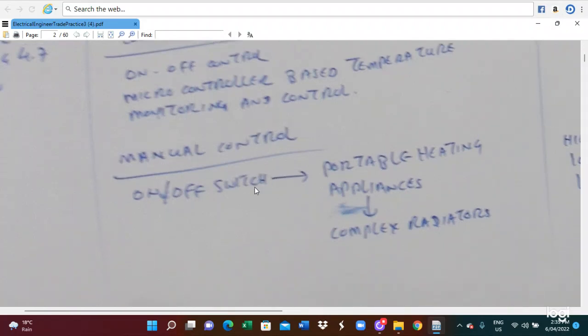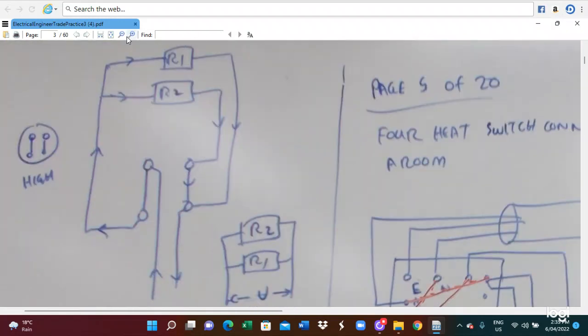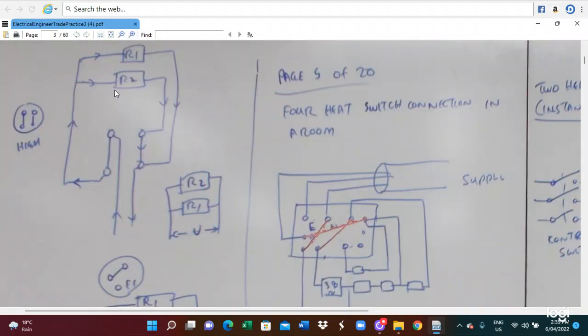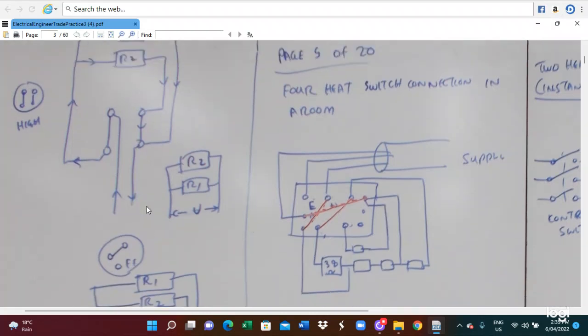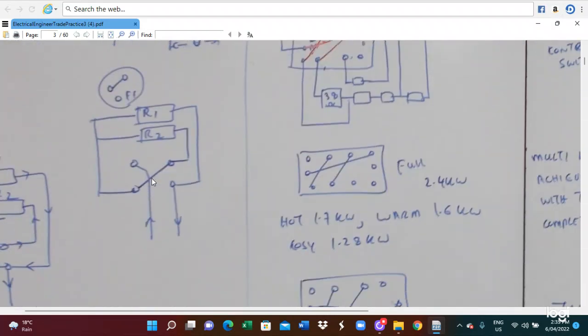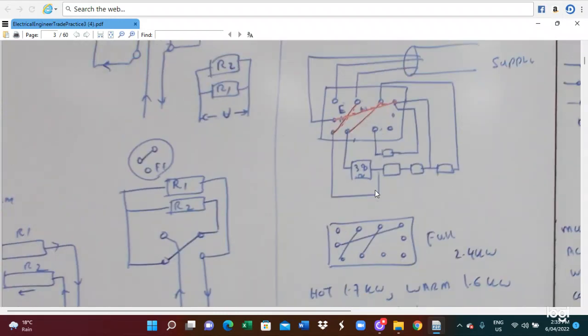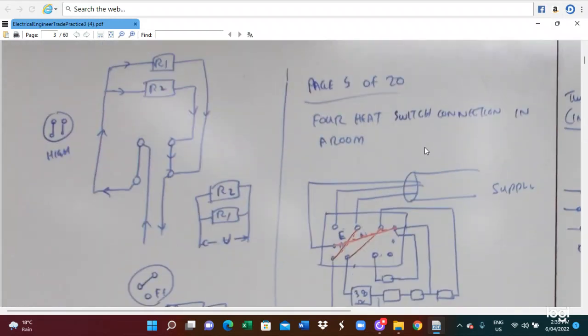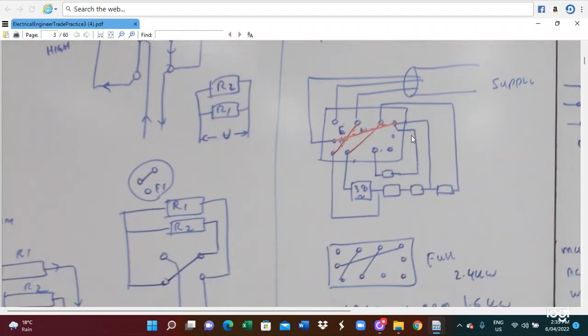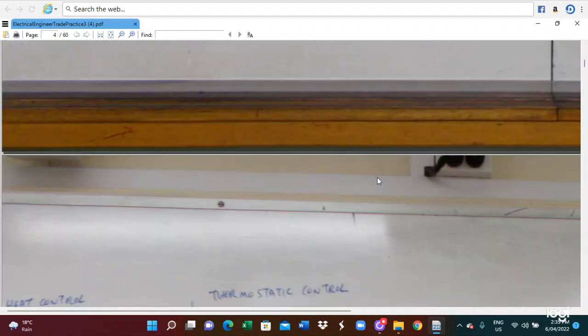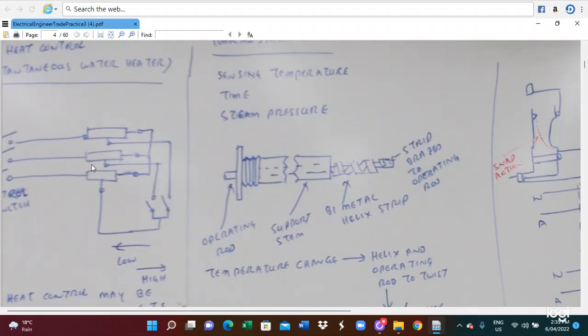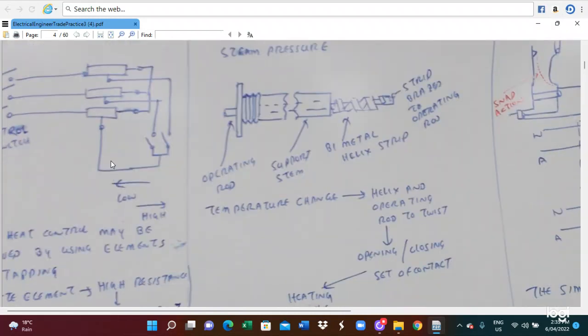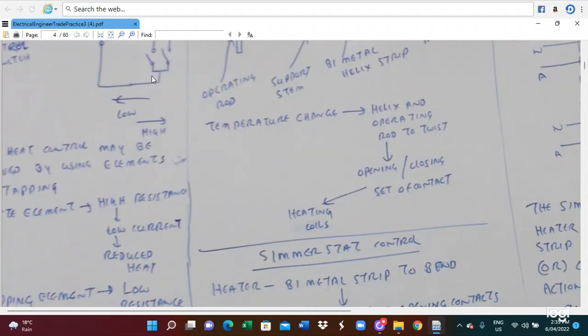Also the manual control system, we utilize the on-off switch and also portable heating appliances, and the complex radiators we utilize with the manual control system. So this is the control circuit for the heating system, resistor, and the high and low wire connection. When the high and low wires are connected like this, here is a control switch connection in the room. So control switch position. Here is the connection of the heat control system. High and low connection, the wire heating coil will be connected.